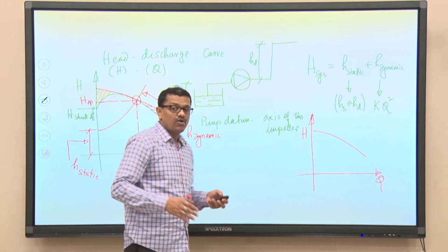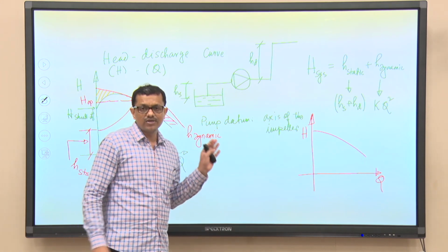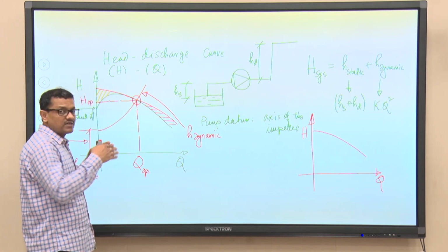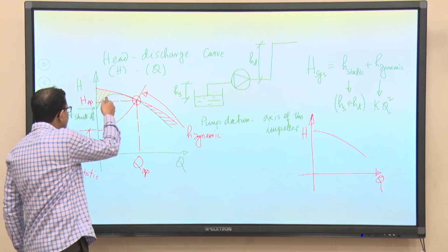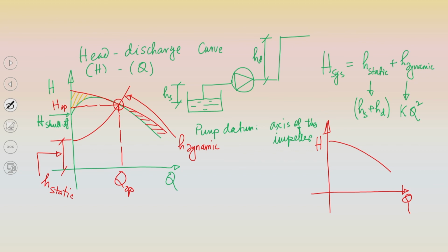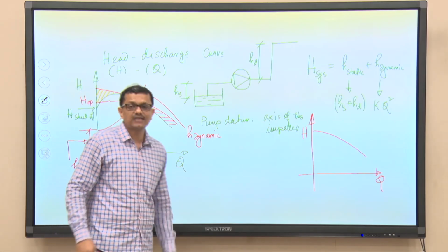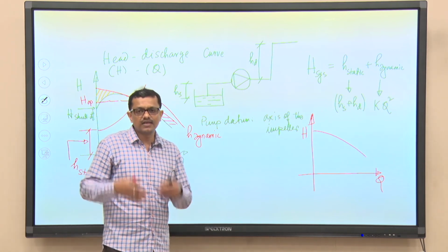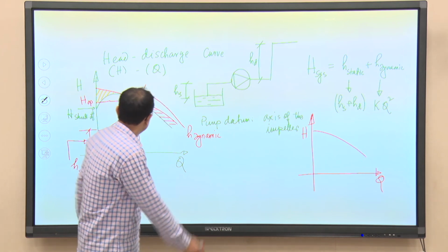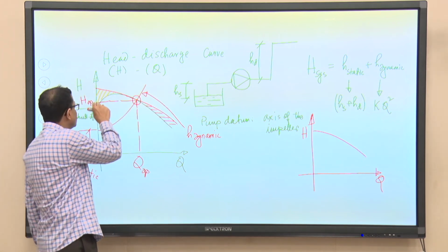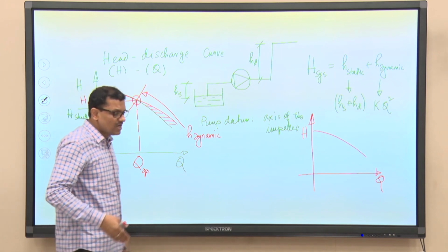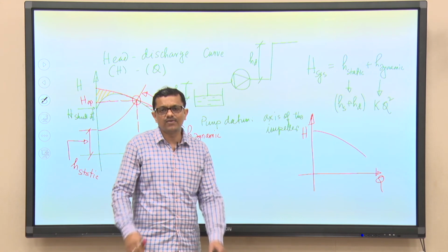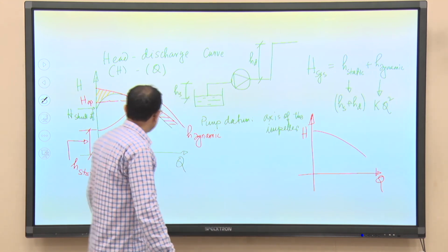Now, why am I going to discuss this aspect? I am not going to discuss the boundary layer development, but at least from the operational point of view of the pump, we should understand that this is not desirable. So, the separation loss at the pump suction side, which will definitely take place, is not desirable at all. What it does, you can see from this diagram, is that the shut off head is getting reduced. Now, if the shut off head is reduced, this is very detrimental for the pump operation, right. Why is it so?